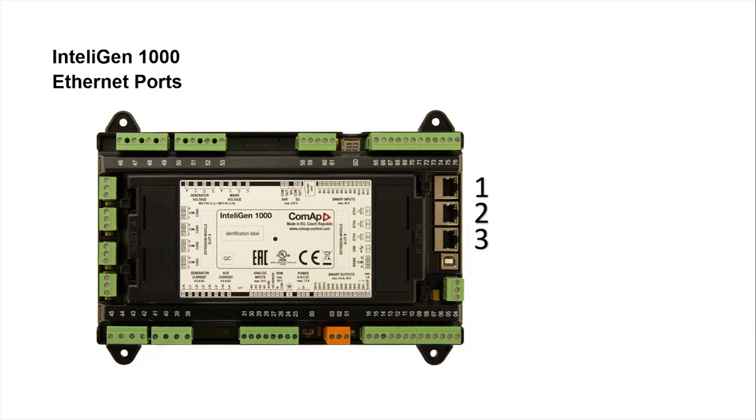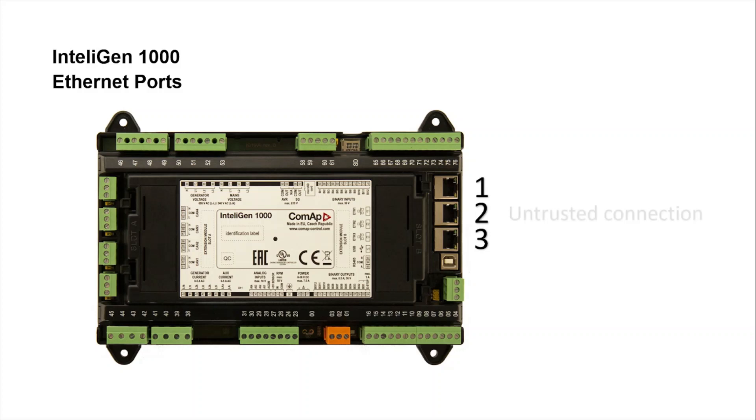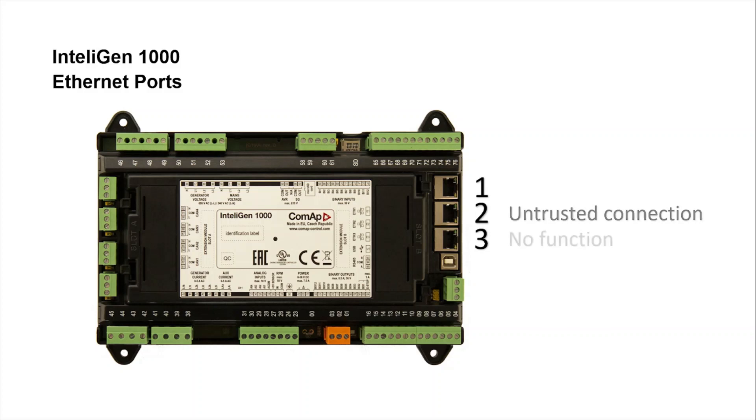The controller has three RJ45 Ethernet ports. Port number one is designed for trusted connections and we can use it to connect directly to a display or for connection to a local network. Port number two is designed for untrusted connections where access must be restricted and you must enter a previously configured username and password. And port number three does not have any function assigned yet.